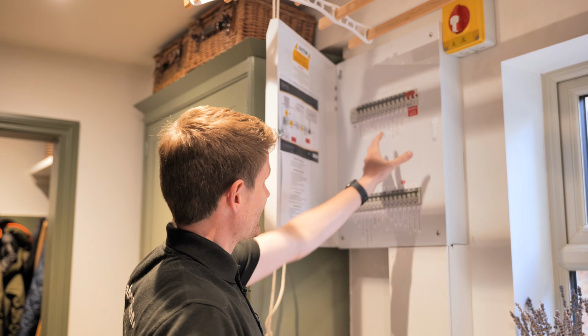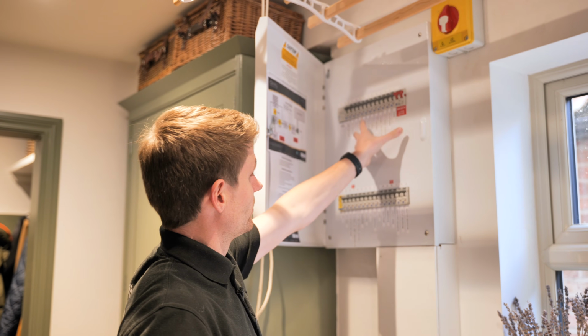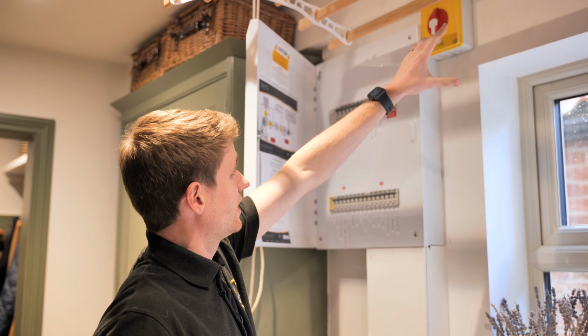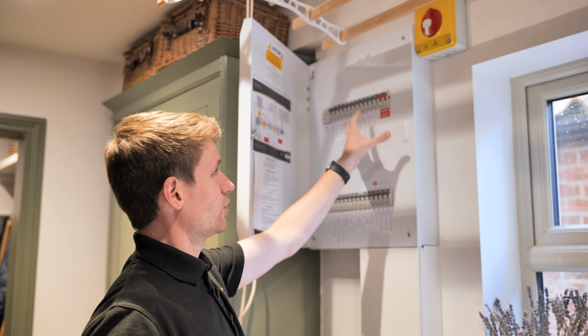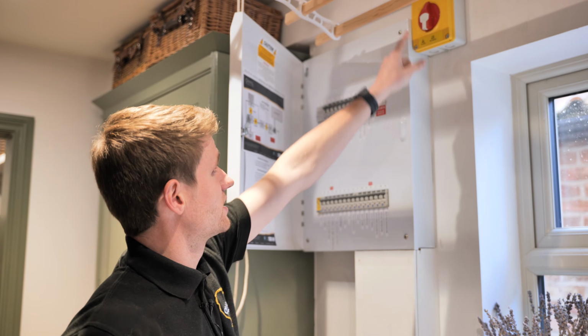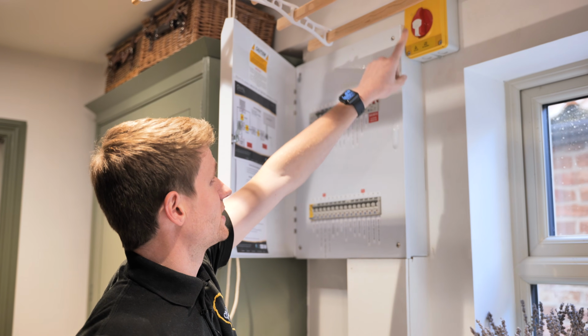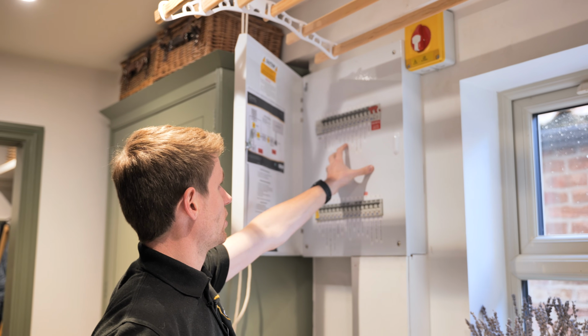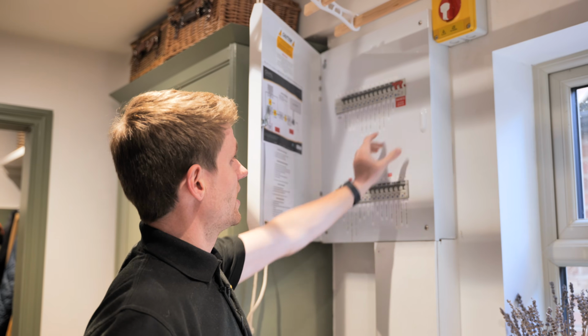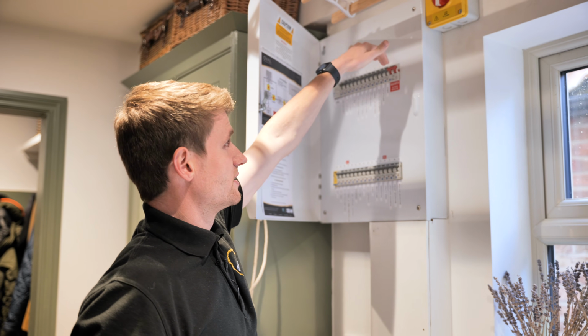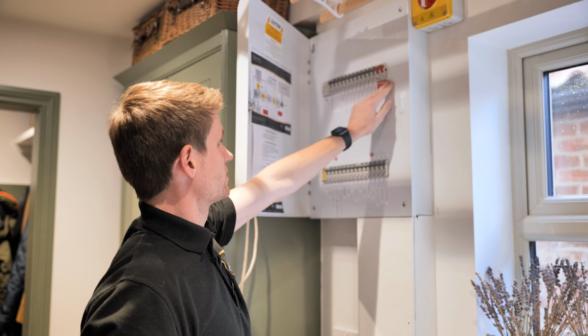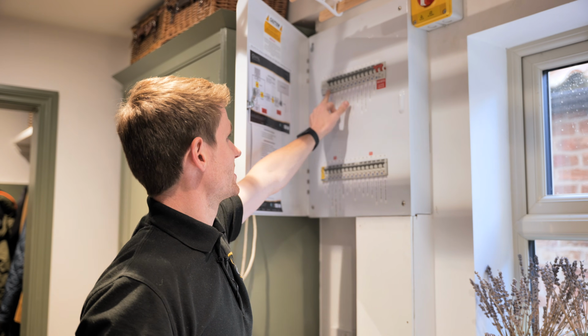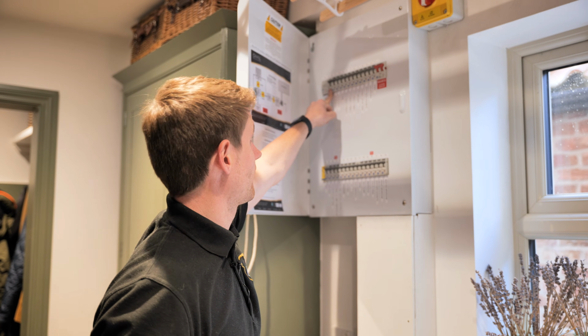That's all nice and neat, and this is really the way the battery can then, if the house needs more power because there's not enough solar to supply all these circuits, the battery will pump the power down through the isolators and into this board, and it'll backfeed these circuits. It'll mean the grid isn't needed to import anything to support any of these circuits, because it's getting its power through this MCB here.